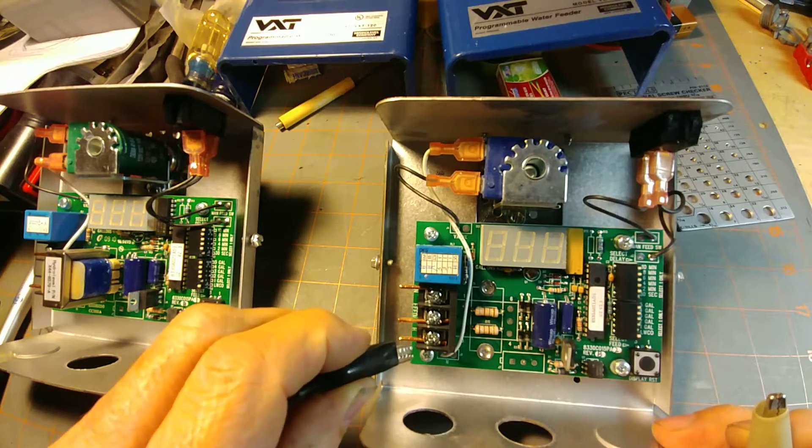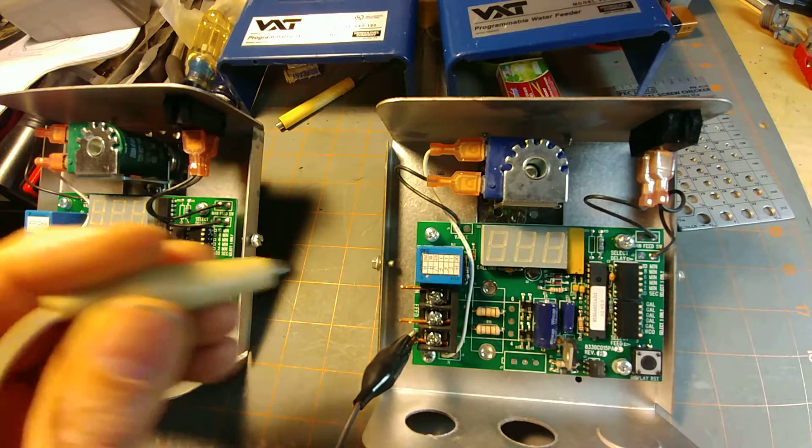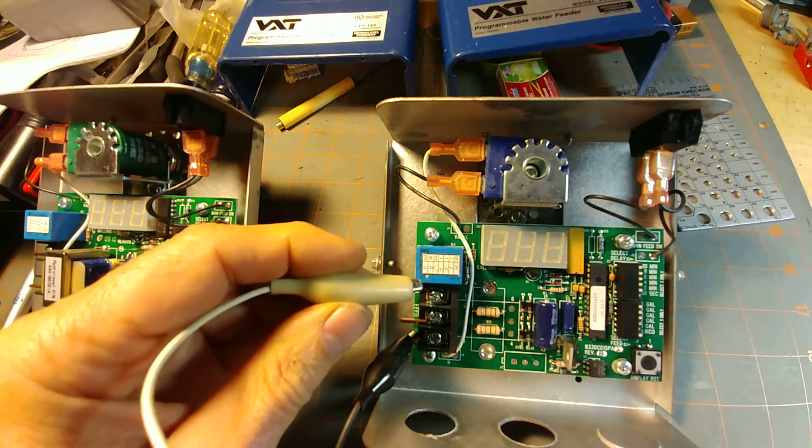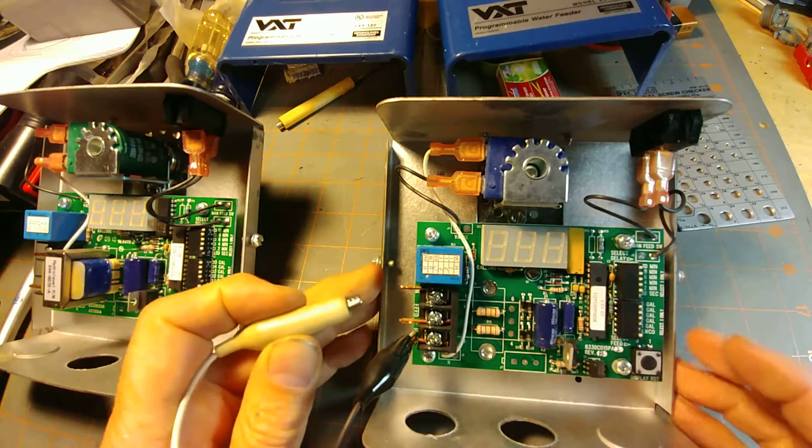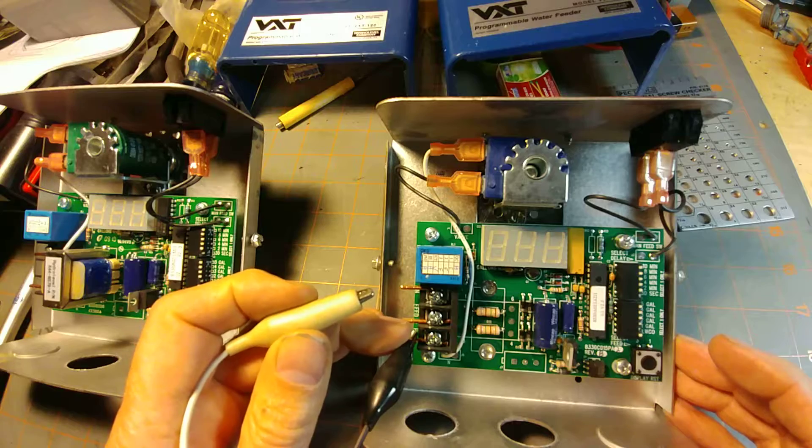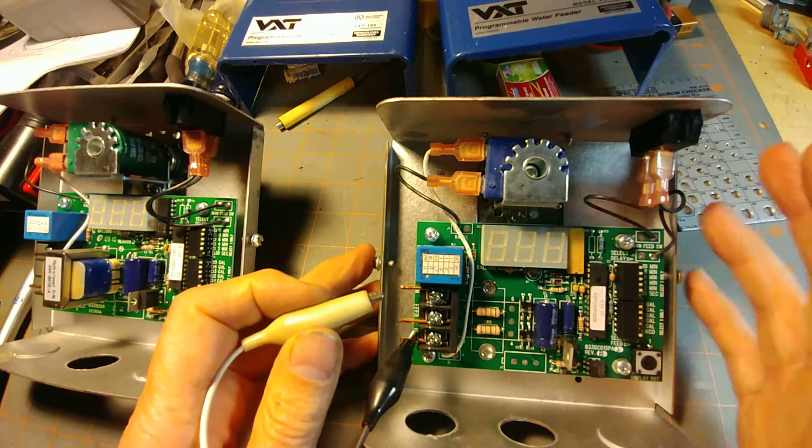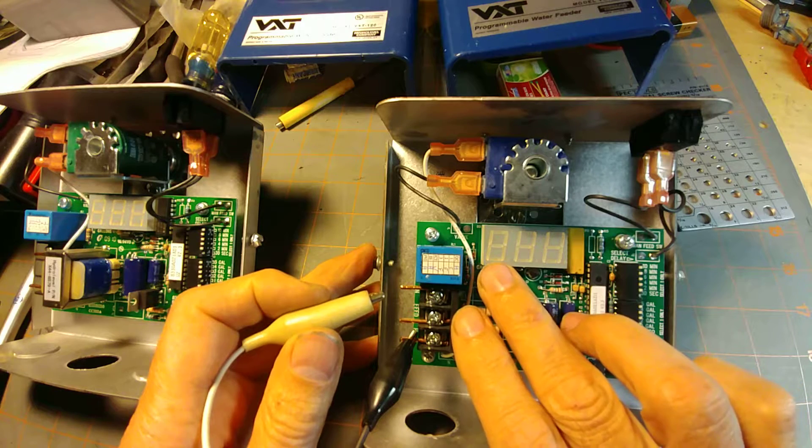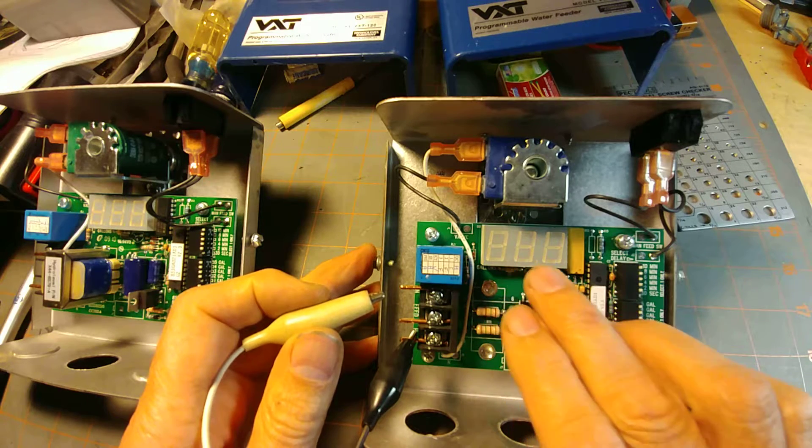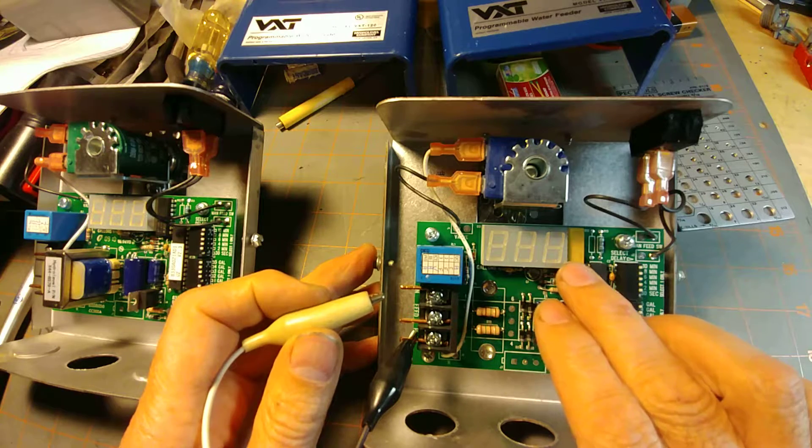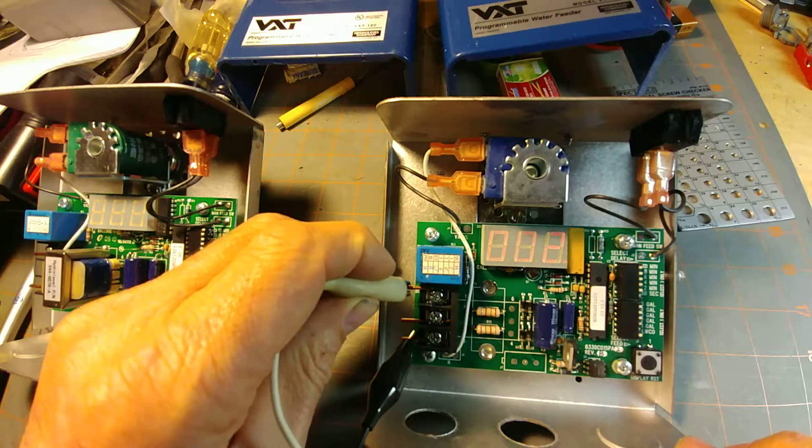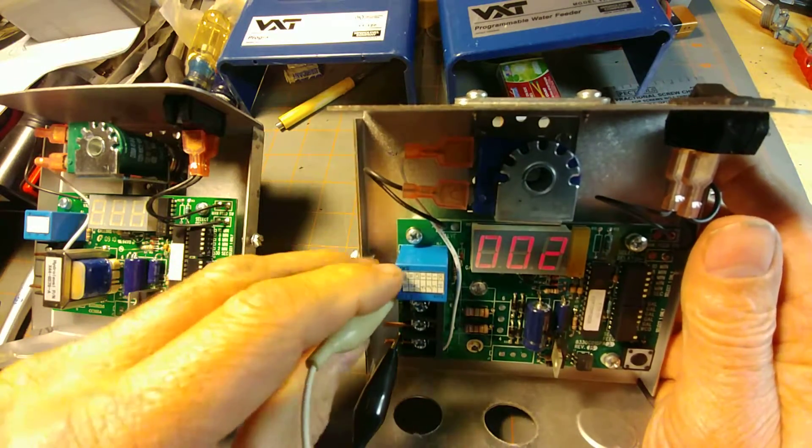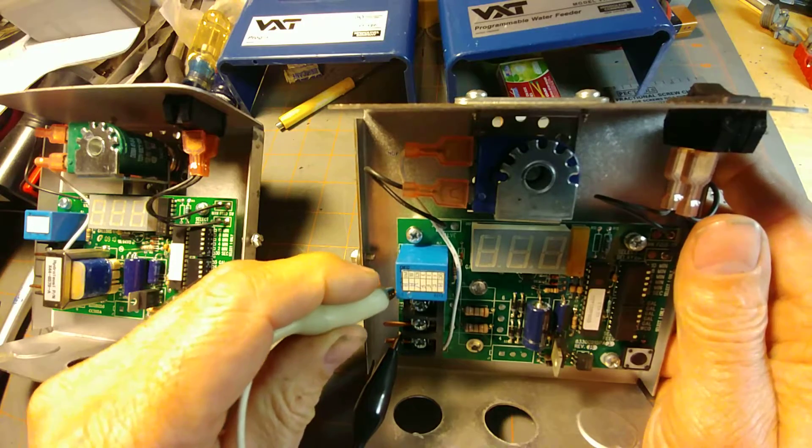You want to run your hot 24-volt lead here. If you have a polarized system, you want to run your grounded lead here. When you light this up and energize this unit brand new out of the box, you're going to see the number zero, then zero, and the number two. Then for about a second, this period is going to light up before it goes out.